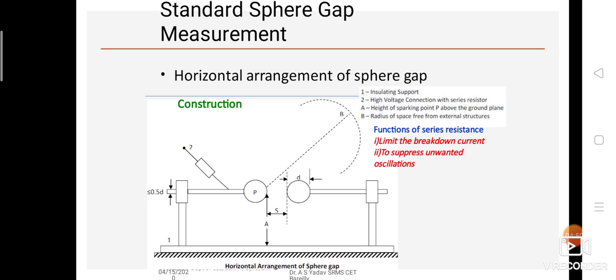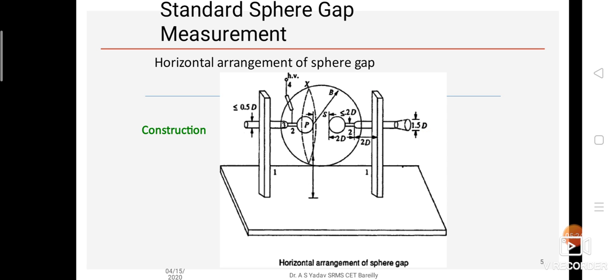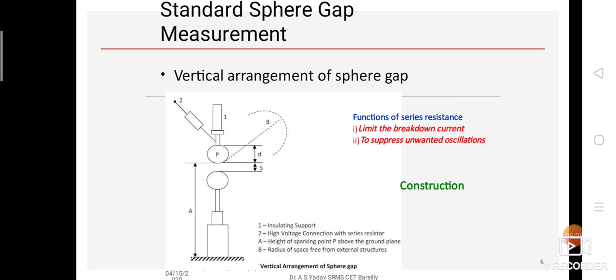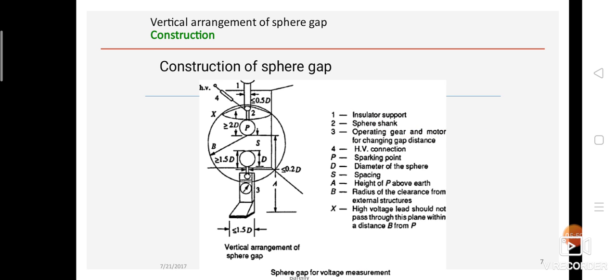Here the figure is given of the horizontal arrangement of the sphere gap. The function of the resistance we have already explained: it limits the breakdown current and suppresses the unwanted oscillations. Here the right hand side sphere is fixed and the left hand side sphere is movable, moving close to the other and far away from it. This is the construction in another view, and this is the vertical arrangement of the sphere gap method. The ground side is fixed and the upper side is movable, and the distance is decreased until the spark over occurs between the two spheres. And this is another view of the vertical arrangement.